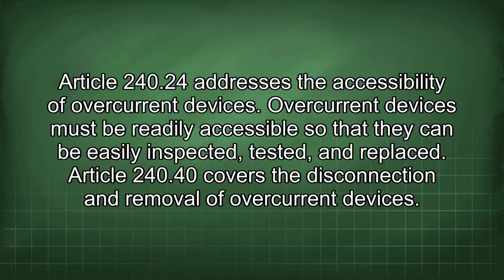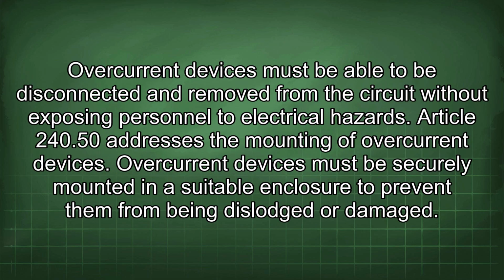Article 240.24 addresses the accessibility of overcurrent devices. Overcurrent devices must be readily accessible so that they can be easily inspected, tested, and replaced. Article 240.40 covers the disconnection and removal of overcurrent devices. Overcurrent devices must be able to be disconnected and removed from the circuit without exposing personnel to electrical hazards.